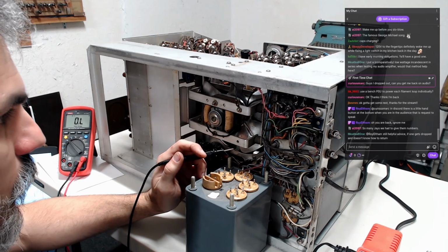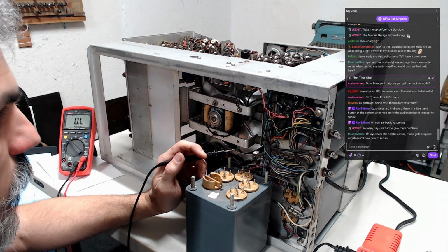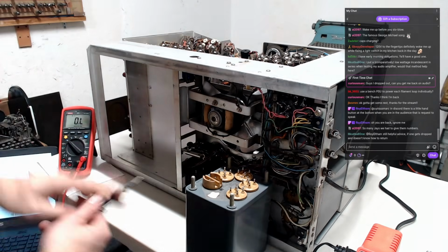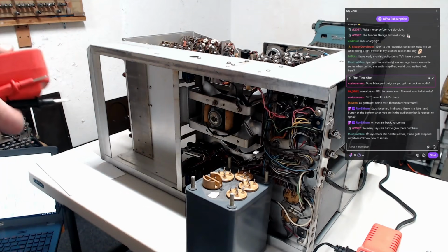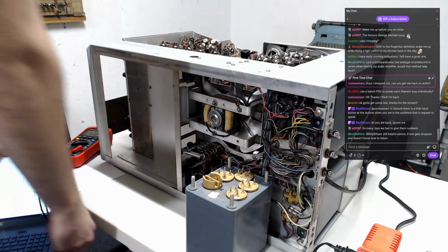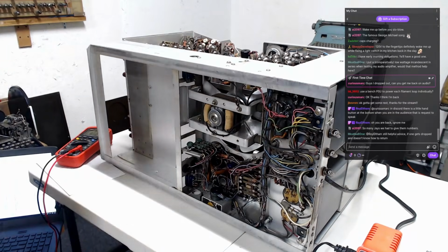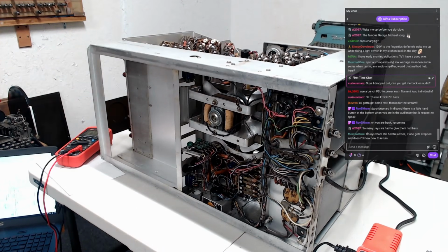You want to try it at low voltage with the variac and see? Yeah, we can, it is transforming. If you set it to something low, like 10 volts or whatever, you can also check the secondaries to see if the ratio gives the correct voltage. Yeah, if it doesn't immediately explode the fuse. Where did I put all my damn fuses? There they are.